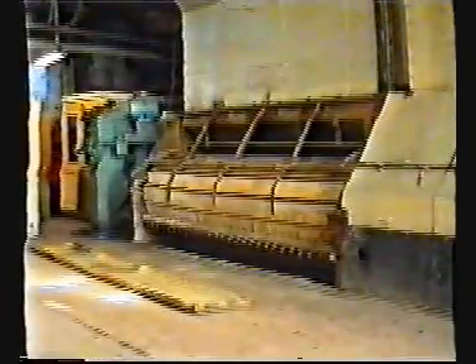Now that the turf is delivered, the next step in the process is the operation of the boiler. In this basic model, the main parts shown are the bunker, the grate at which the turf is burnt, and the water tubes. The turf is fed from the bunker through the turf shaft onto the grate. This grate is a steel conveyor belt made up of 18,000 individual links. The agitator loosens up the links to allow air to pass up through the grate for combustion purposes. Each boiler has 2 grates.